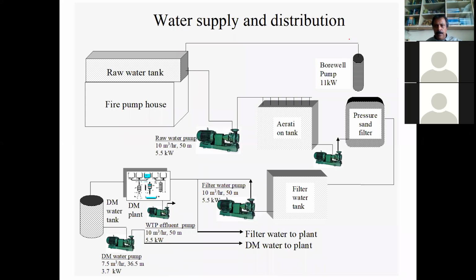The bore well was pumping the water to a raw water tank, which was above the fire pump house. From the raw water tank, the water was taken by a pump and first aerated. Spray nozzles here, aeration was done. When we asked the plant people what is the purpose of aeration, why this process is there, the water treatment person was also not very clear.